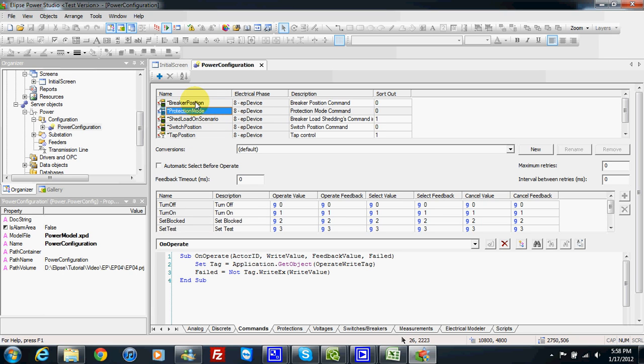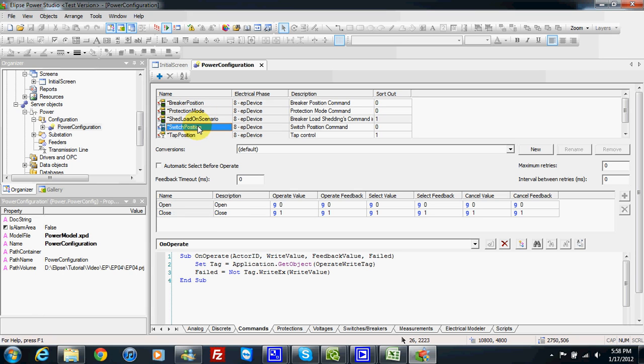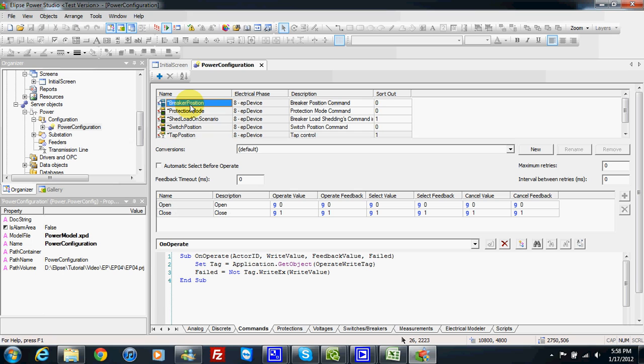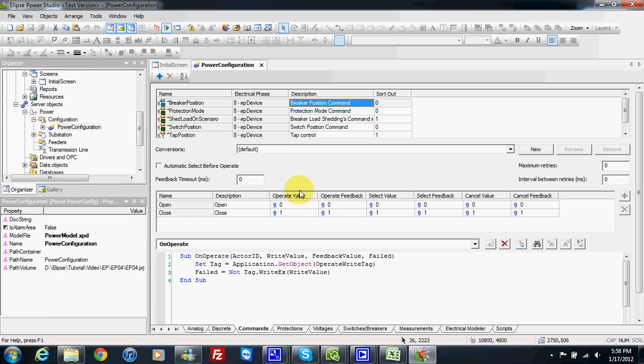The command types include breaker position, protection mode, shed load on scenario, switch position, tap position, and transformer commands. For a breaker position example, we have the breaker position command, and here we have different values taken from the different stages of the command. For example, we have first the select value, then the operate value. If you want to make a command for select before operate, we can also choose this mode.